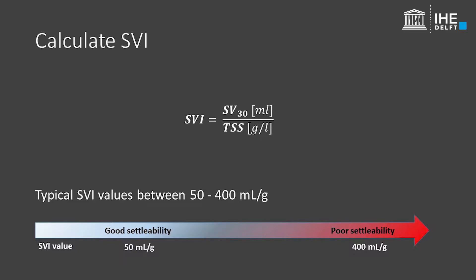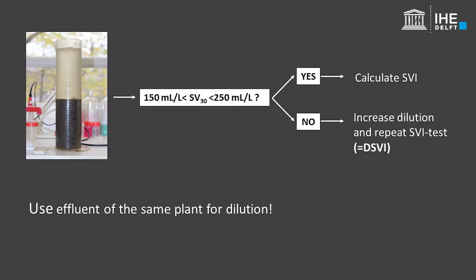If the measured volume after 30 minutes of settling is not between 150 and 250 millilitres, it is recommended to redo the test by either diluting or concentrating the sludge until the final volume is situated between the boundaries of 150 to 250 millilitres per litre. This is then called a diluted SVI test.